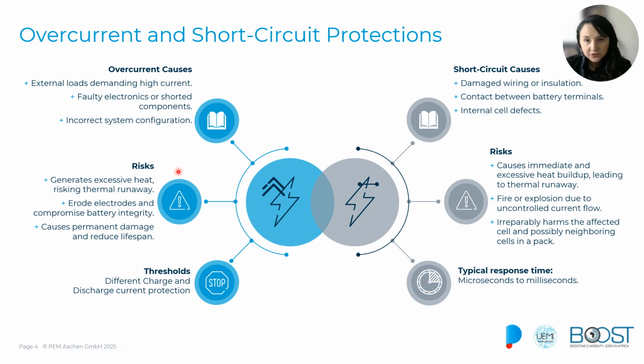The overcurrent conditions are critical because when we have overcurrent, usually we generate excessive heat, and this can damage the cells and the electrode materials, as well as compromise in general the safety integrity and the lifespan of the battery. And the most dangerous is that the excessive heat that is generated can lead, for instance, to thermal runaway and again increase the risk of fire or explosion. It is important to notice that in a battery, the charge and the discharge current ratings are different. Usually the overcurrent limit in discharge is much higher than the overcurrent limit in charge.